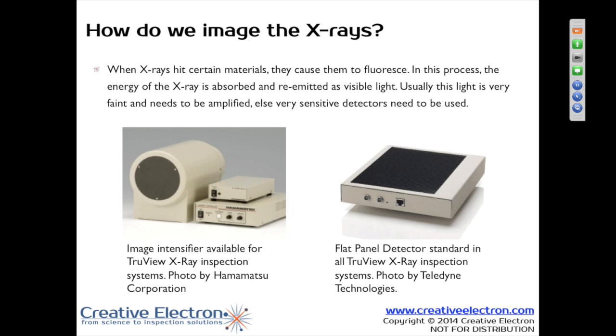So to get the same amount of output, you would have to kick up your kV and mA. Although you can do magnification and the magnification is actually pretty decent, image intensifiers tend to be very dependent on the amount of energy applied to them and the amount of light. Since they are a vacuum tube, similar to a CRT, they are very susceptible to burn-in. If you take a component and leave it in the image for a couple of hours and somebody walks away from the x-ray system, you can actually burn that detector to the point where it's unusable.